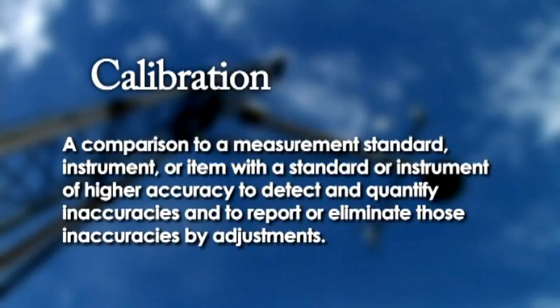Before we get going, let's define what we mean by a calibration. EPA defines a calibration as a comparison to a measurement standard, instrument, or item with a standard or instrument of higher accuracy to detect and quantify inaccuracies and to report and eliminate those inaccuracies by adjustment.